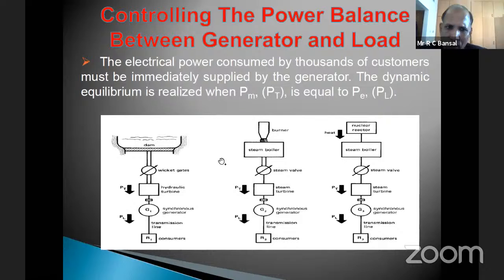Here, all these different generating plants are interconnected through the transmission network. If we see the control for any individual generator or plant, there will be appropriate control, like in the coal-based power plant, there is control for the steam through the steam valve control. Even in nuclear, we have similar control. If you have large hydro, there is control for the passage of water through the hydro turbine. So this control is very important.